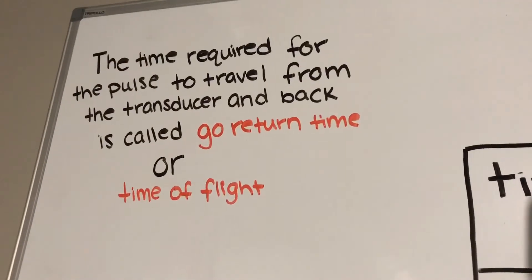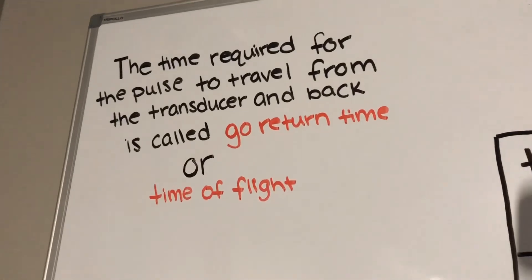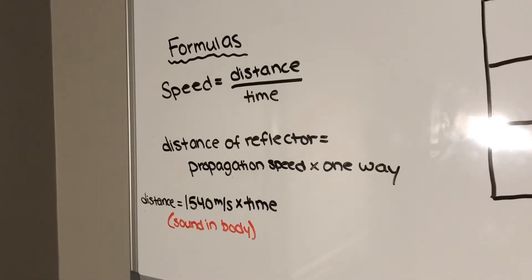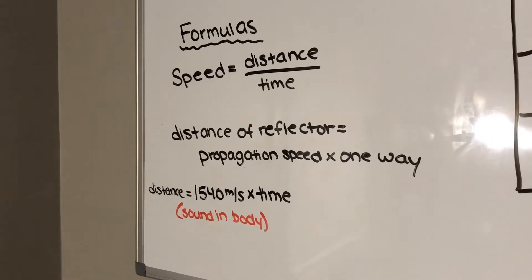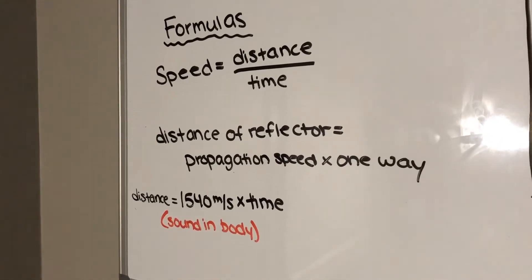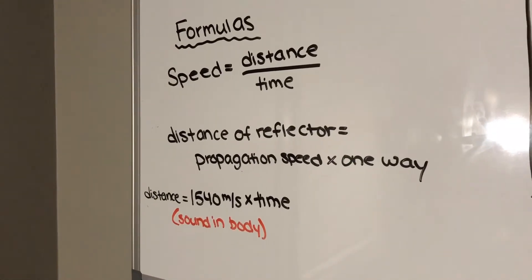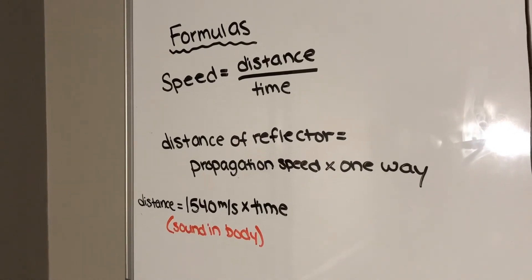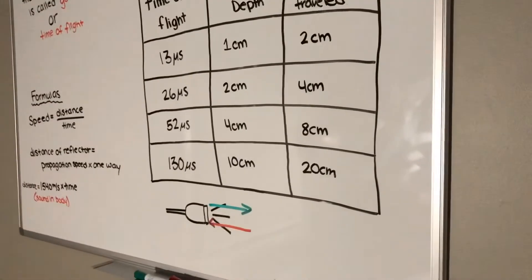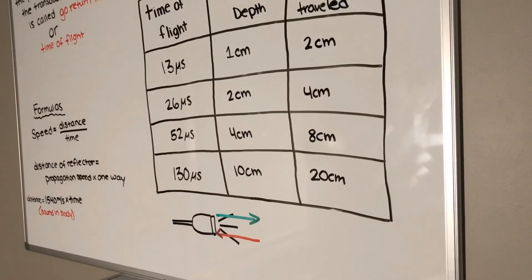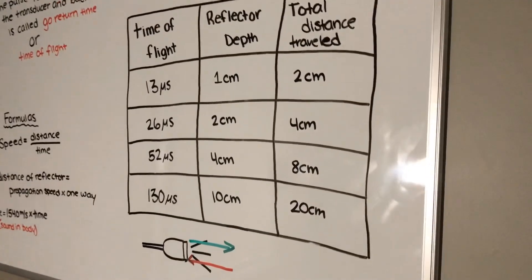The time required for the pulse to travel from the transducer and back is called go-return time, or time of flight. The formulas you want to know for this chapter is speed equals distance over time, distance of the reflector is equal to propagation speed times one way, and distance equals 1540 meters per second times time, and that is the sound in the body. In soft tissue, every 13 microseconds of go-return time means the reflector is one centimeter deep in the body.